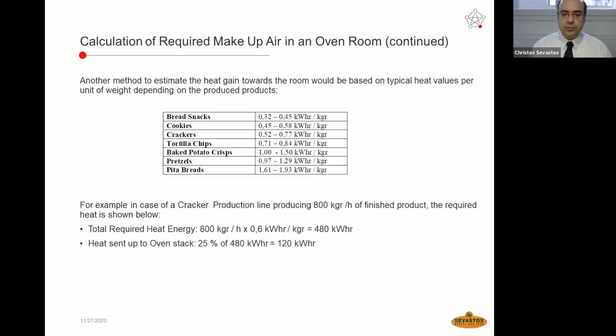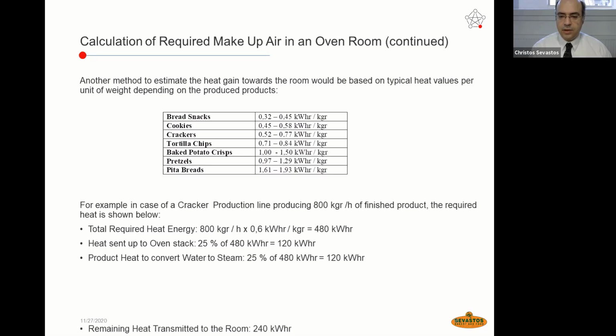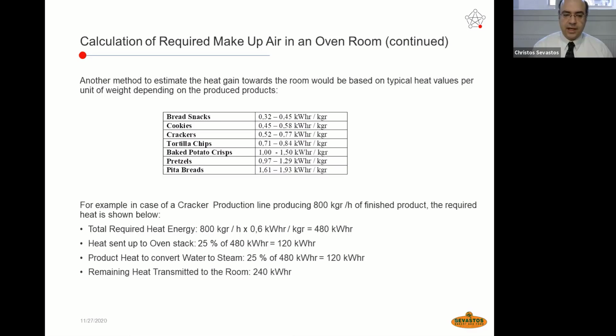The heat sent up to the oven stack is 25% of the 480 kilowatt hour, so it's 120 kilowatt hour. The product heat, in order to convert water to steam, is 25% of 480, which is the overall heat energy, so it's again 120 kilowatt hour. The remaining heat transmitted to the room is 240 kilowatt hour. This is the internal heat load in areas where we are going to have tunnel ovens.